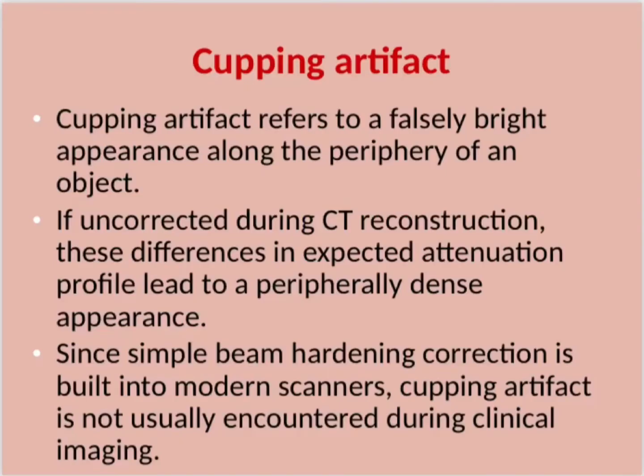Cupping artifact refers to a falsely bright appearance along the periphery of an object. If uncorrected during CT reconstruction, these differences in expected attenuation profile lead to a peripherally dense appearance. Since simple beam hardening correction is built into modern scanners, cupping artifact is not usually encountered during clinical imaging.